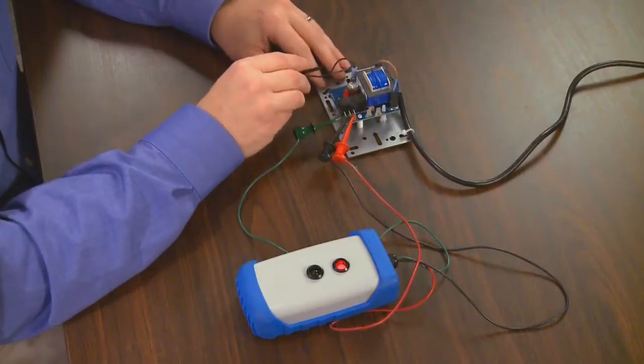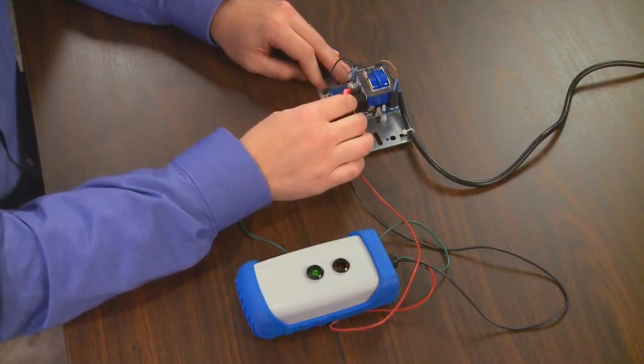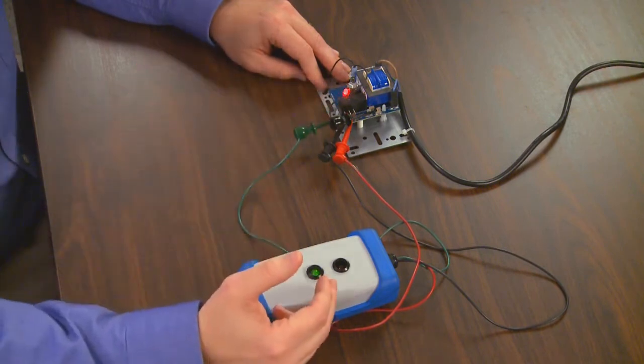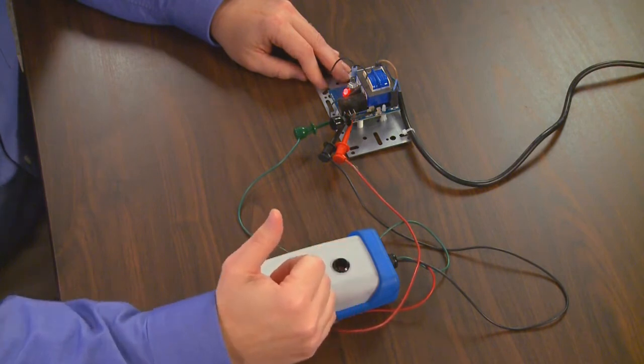Now in a single level service direct mode, when water hits the high probe, the LED comes on, relay is energized, you notice that the lights have changed state. The normally closed contact becomes open, the normally open contact is now closed.